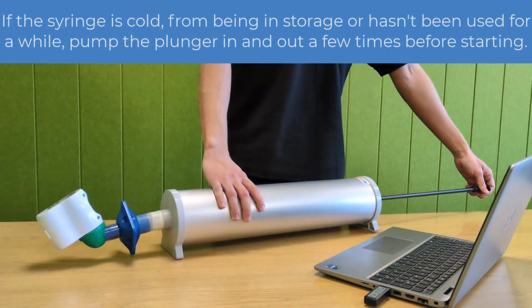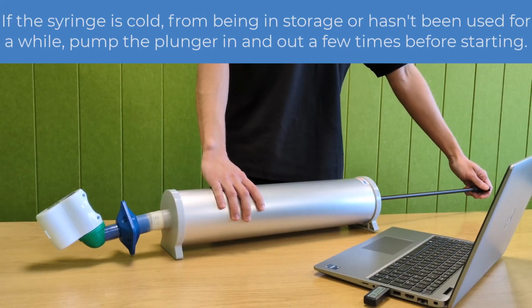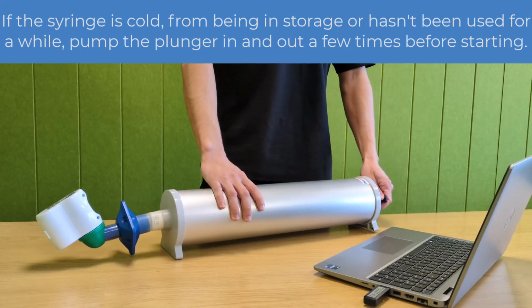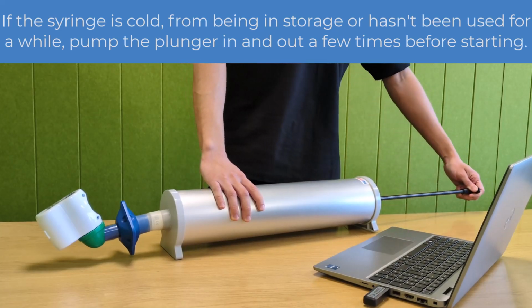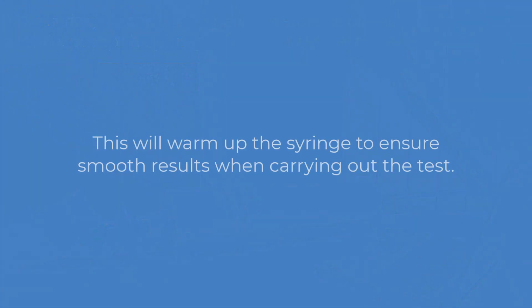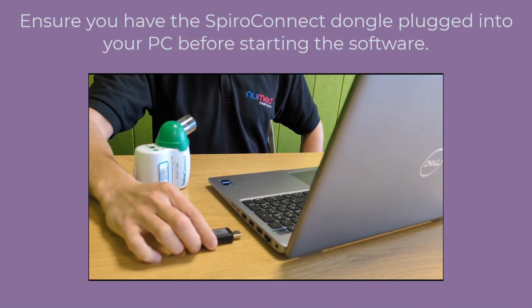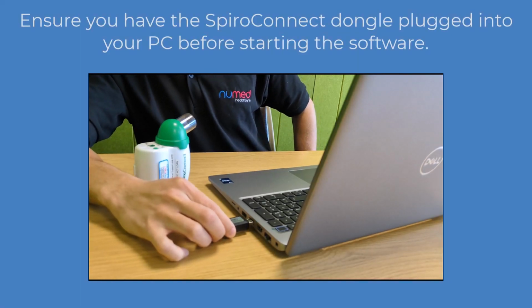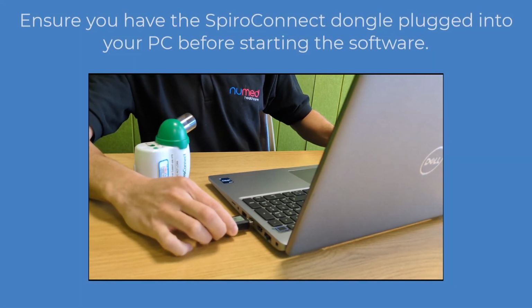of the test. If the syringe is cold, from being in storage or hasn't been used for a while, pump the plunger in and out a few times before starting. This will warm up the syringe to ensure smooth results when carrying out the test. Ensure you have the SpiroConnect dongle plugged into your PC before starting the software.